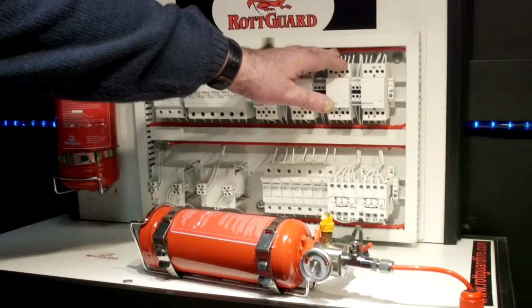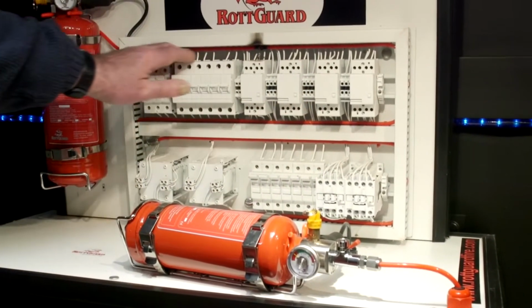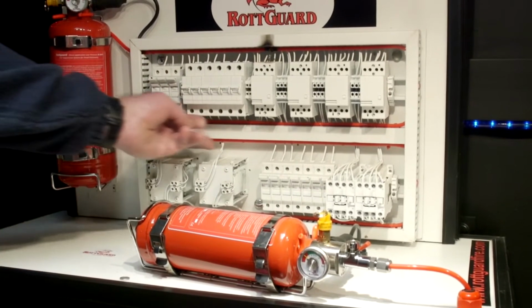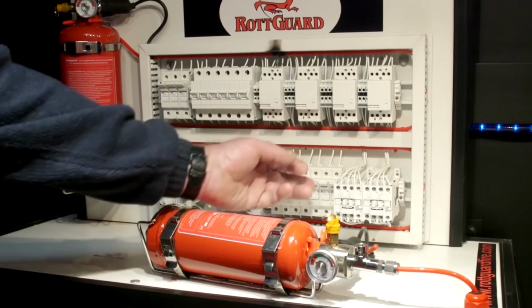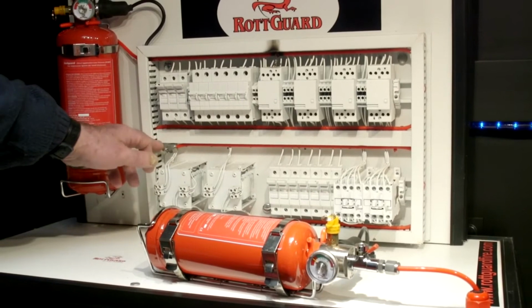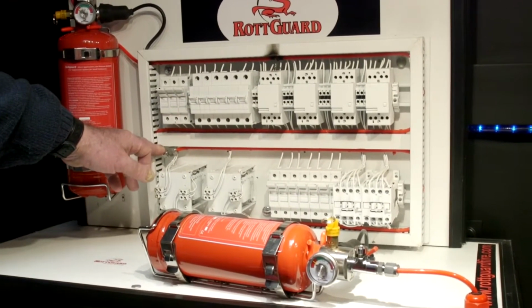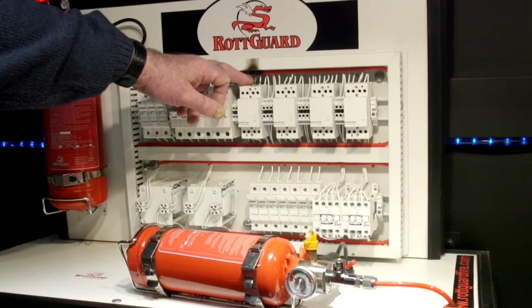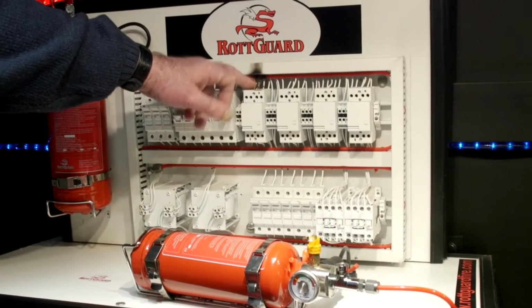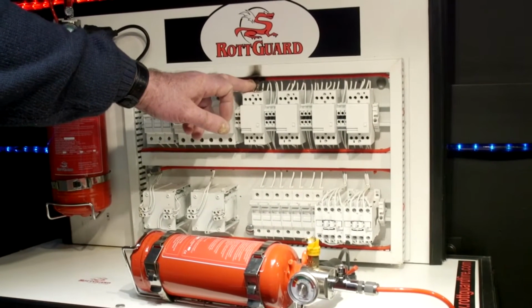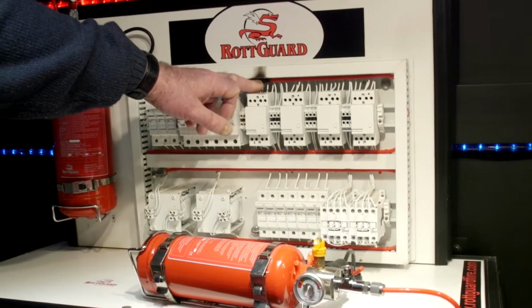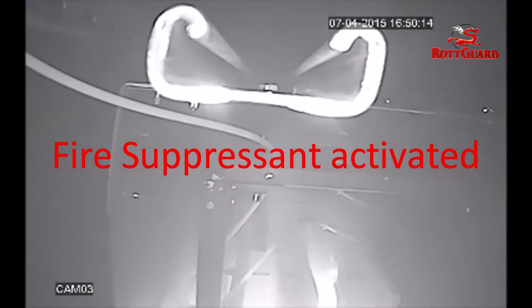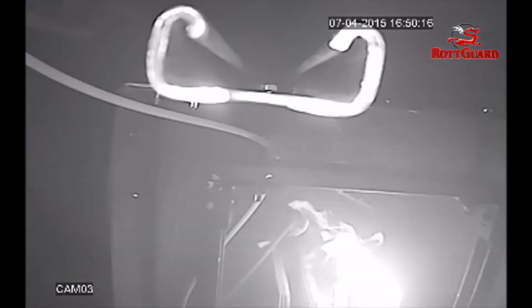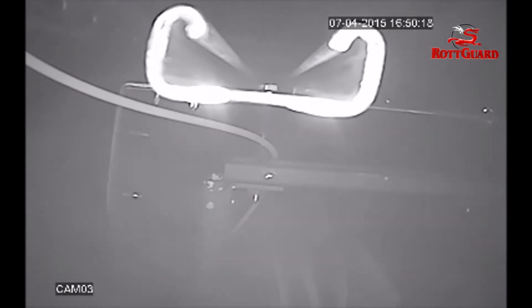The tube is attached neatly to the underside of the trunking across over each of the pieces of switchgear, and it's terminated down here at the end. This represents here where a cable has gone on fire, and the heat from that fire was sufficient to rupture the tube here. It would have extinguished the fire instantly and left no residue and would have had no impact on anyone within the room.